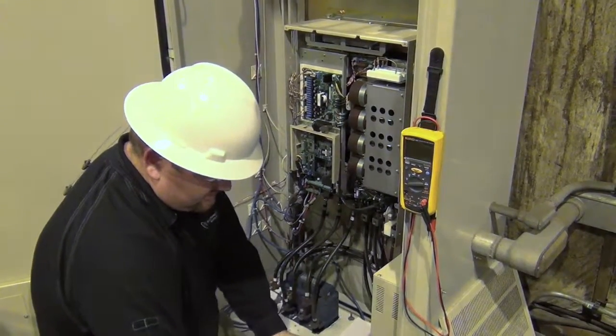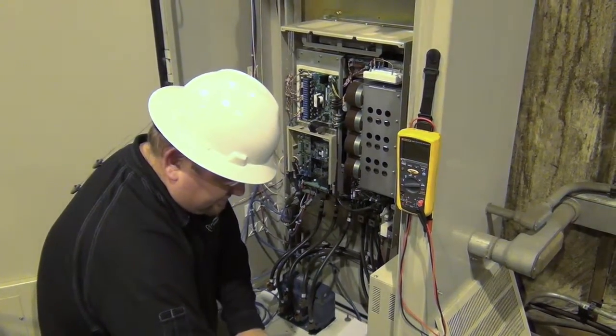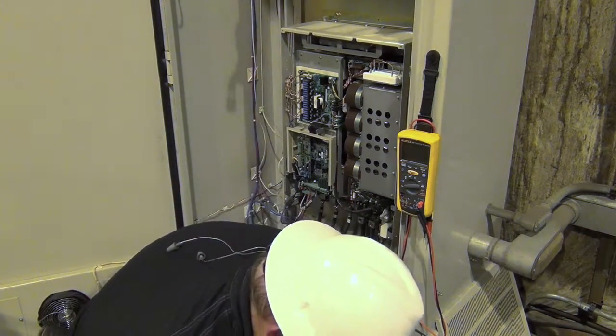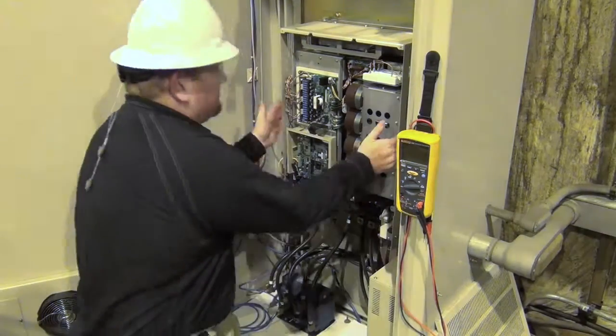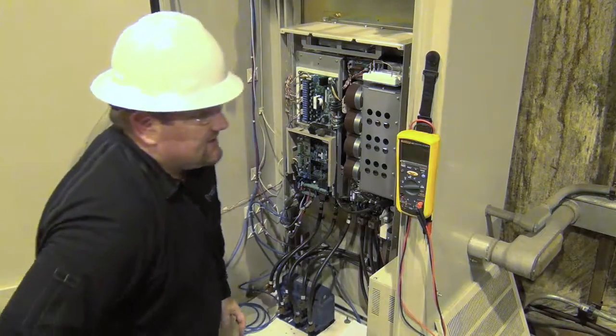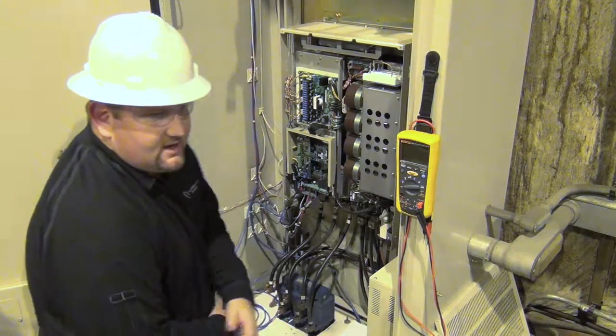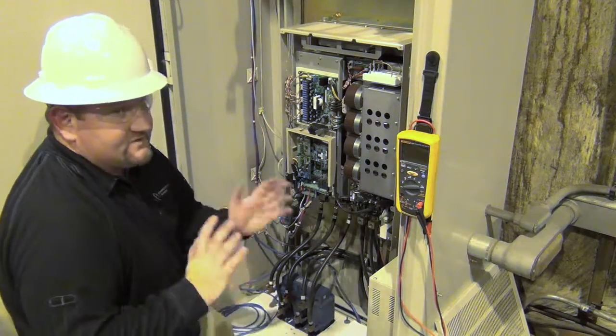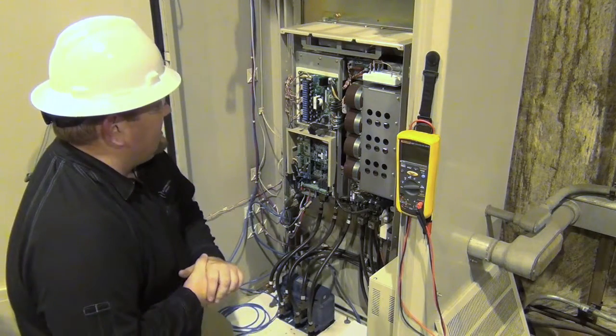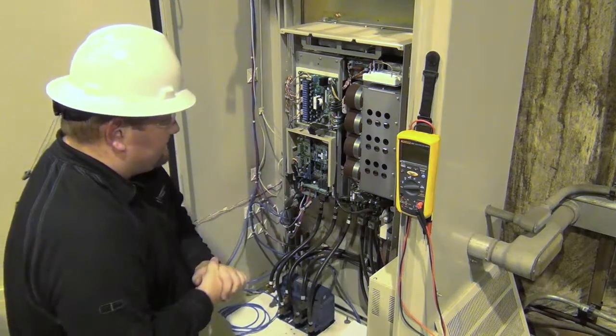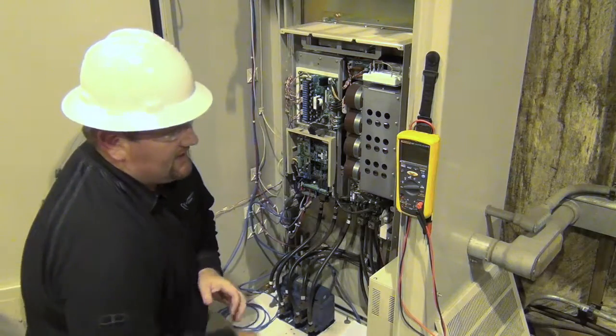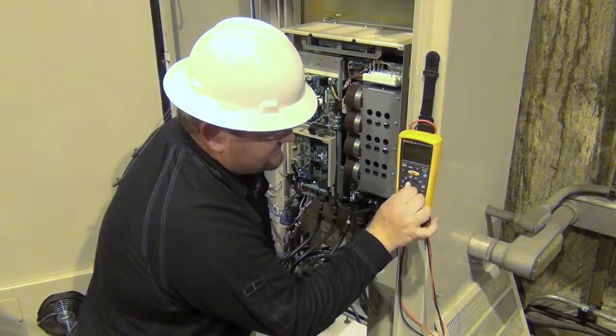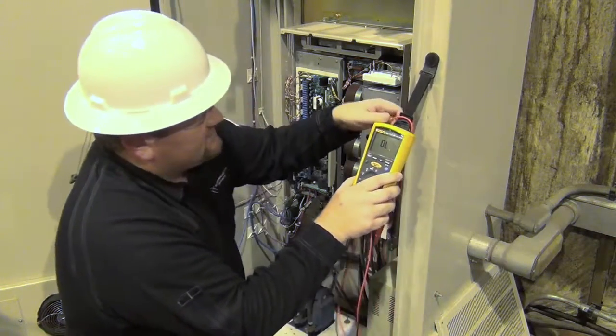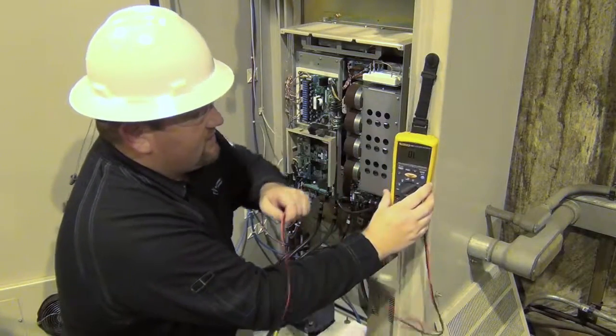So next thing we're going to do is do an input and an output check on the drive. For the input of most drives, this particular model is a diode-based front end. Some drives are an SCR type front end, and they'll have a different set of readings. But for today's demonstration, we're going to do it on this drive. So in order to do this test, you need to have a meter that's capable of a diode check function.